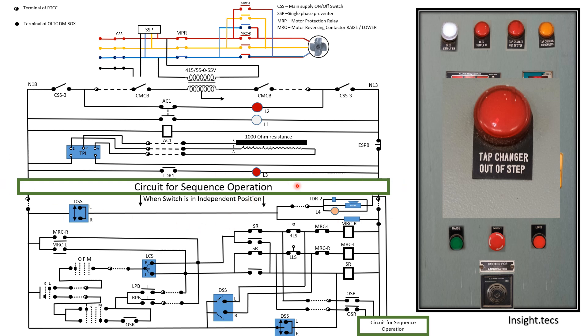This green box indicates the circuit for sequence operation. Whenever there are multiple transformers in a substation — say two or three transformers — the sequence of operation for tap changing is set so that whenever the master is operated, the followers will also change their tap position subsequently. Or whenever they are put into independent position, they will change independently. We will learn the circuit for sequence operation in another video; for now we will just take the output from this and learn how the further control circuit operates.